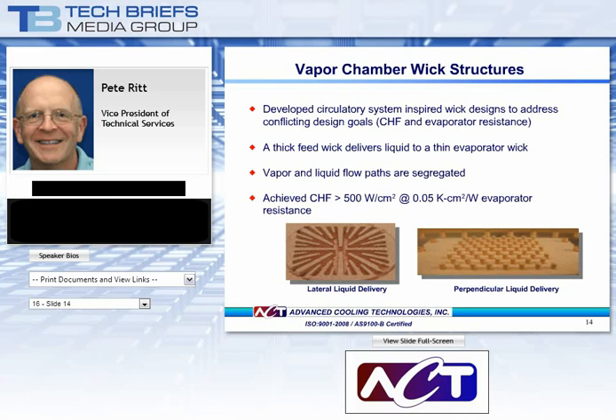Vapor chamber wick structures. ACT has developed a unique circulatory system wick structure to address the conflicting needs of high critical heat flux and low evaporator resistance. CHF, critical heat flux, is a thermal limit where the vapor covers the entire surface, causing it to heat up rapidly. In the novel system being described here, a thick feed wick delivers liquid to a thin evaporator wick. The vapor and liquid flow paths are segregated, but they are co-located.